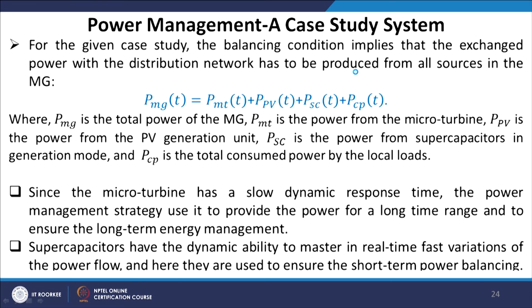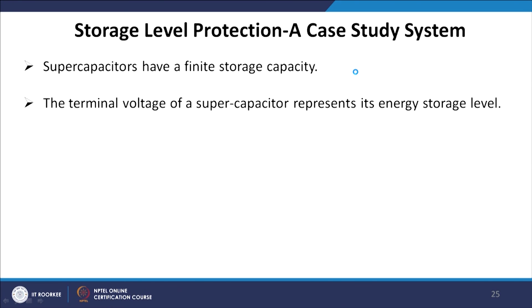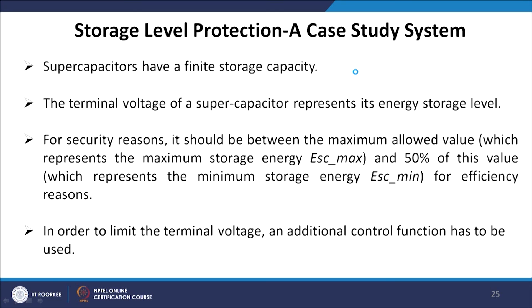Since the micro turbine has a slow dynamic response, the power management strategy uses it to provide power over a long time range, ensuring long-term energy management. The super capacitor, having a dynamic ability, manages real-time fast variations of power flow and is used to ensure short-term power balancing. Super capacitors have finite storage capacity — their terminal voltage represents their energy storage level. For security reasons, the voltage should be between the maximum allowed value, representing maximum stored energy, and 50 percent of this value for efficiency reasons, representing the minimum storage. An additional control function is used to limit the terminal voltage.